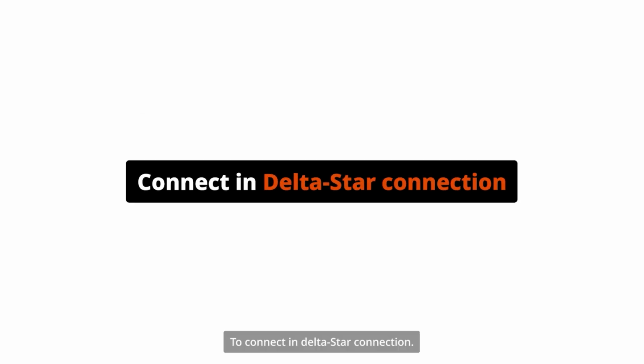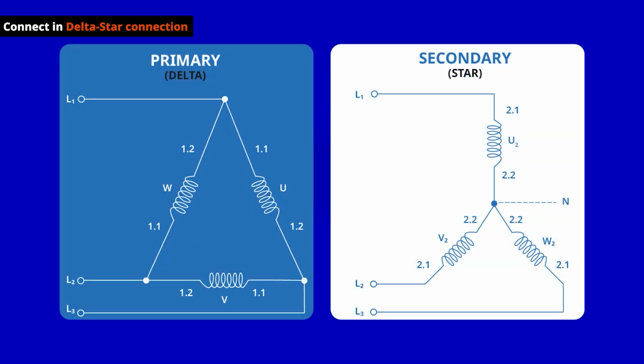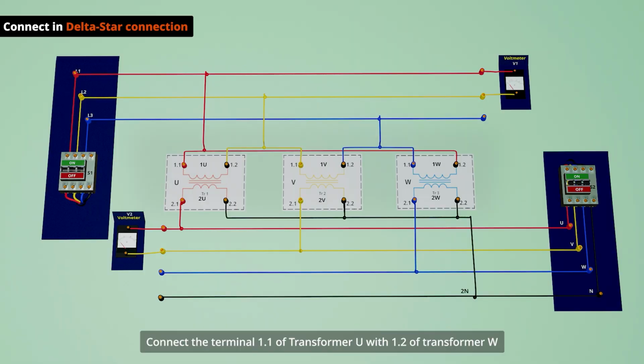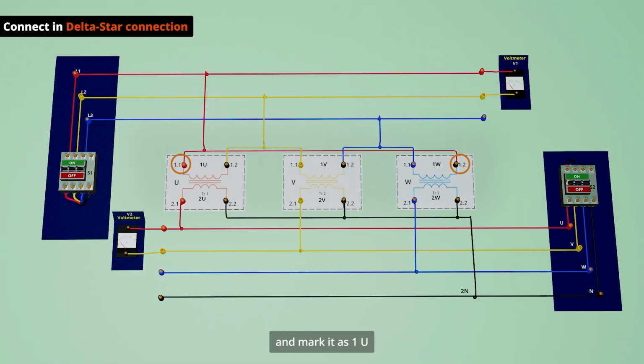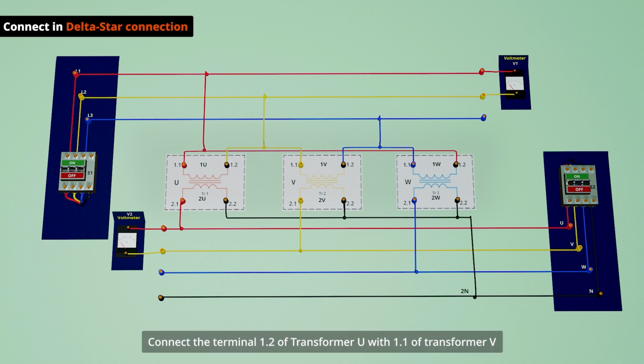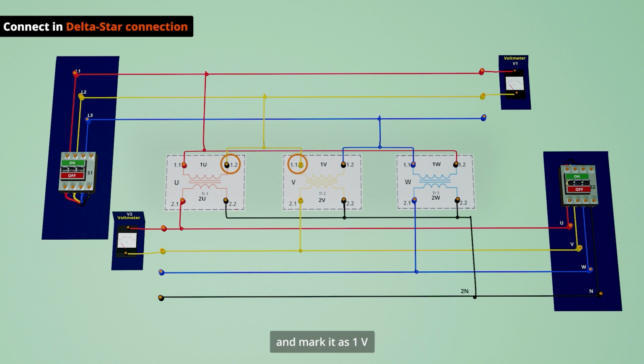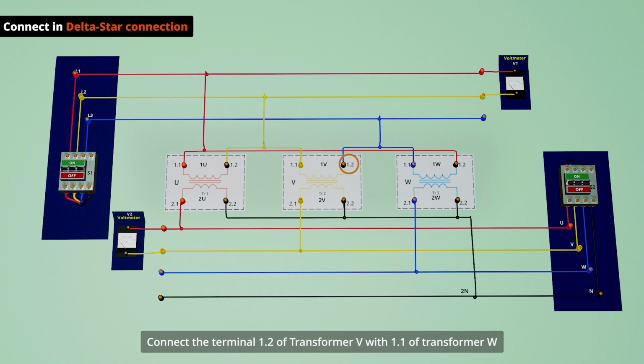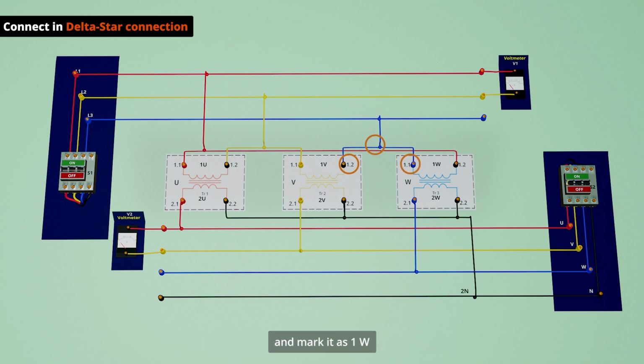To connect in delta star connection, connect the dissimilar terminals of the primary windings. Connect the terminal 1.1 of transformer U with 1.2 of transformer W and mark it as 1U. Connect the terminal 1.2 of transformer U with 1.1 of transformer V and mark it as 1V. Connect the terminal 1.2 of transformer V with 1.1 of transformer W and mark it as 1W.